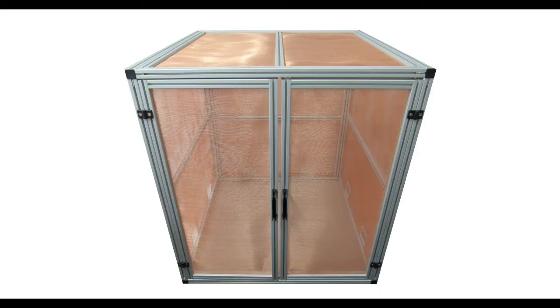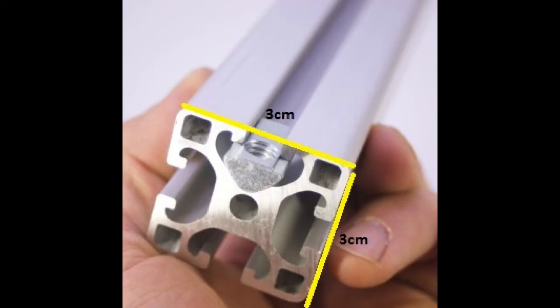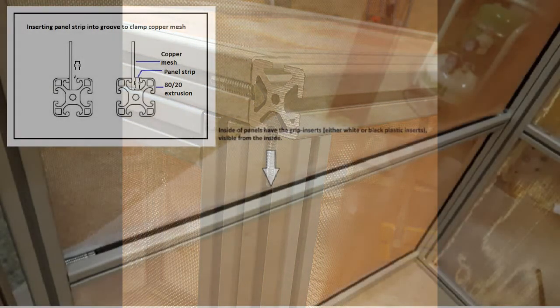The open source Faraday cage bill of materials calculator is based upon a design used in several labs, with the structure of the frame consisting of 80-20 T-slot aluminium extrusion rails with 30mm sides. These rails can be ordered in pre-cut format to save time during assembly. The rails are assembled by clamping the pieces at right angles using 90-degree connectors and using pre-cut copper mesh as the isolation material. The copper mesh is clamped into the frame by compatible infill strips.